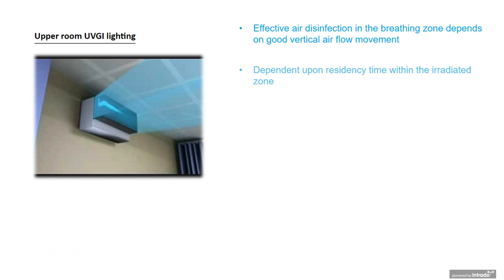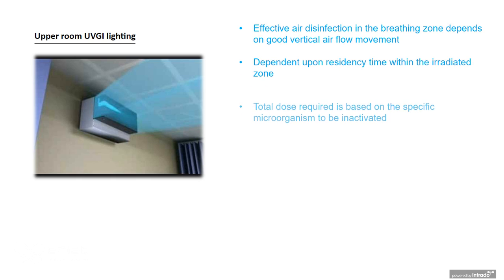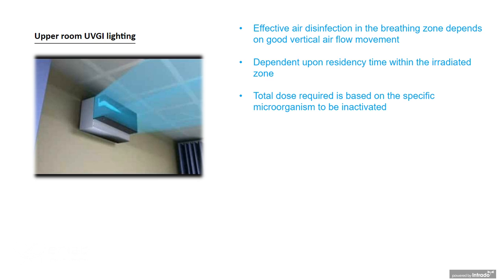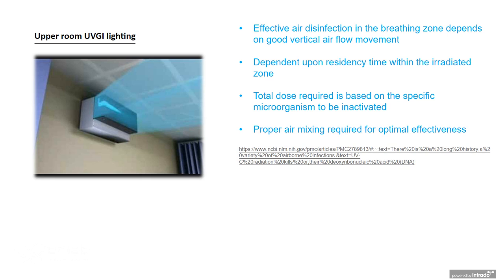So the first technology I want to discuss is upper room UVGI lighting. Traditionally, this has been used in tuberculosis isolation rooms where you have the right, proper directional airflow patterns. It's effective. Upper room UVGI is extremely effective, but you must make sure you have, again, effective room distribution patterns, and you have the proper residency time within the irradiated zones. Total dose required is based on the specific microorganisms to be inactivated. And again, the directional airflow patterns. If you don't have proper upstream airflow, how are we getting the pathogens to this upper room UVGI? So again, a lot of things we have to look at when we're trying to decide which types of technology to integrate into your facility. And there's additional information right on this link that will be available to you when you download the presentation.